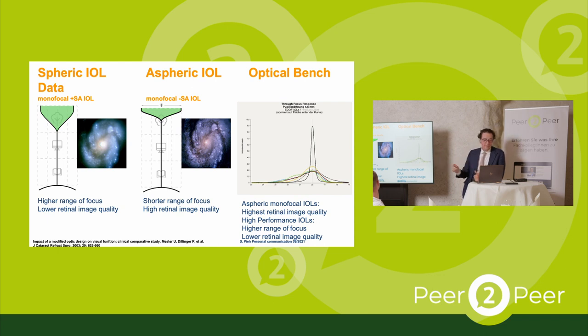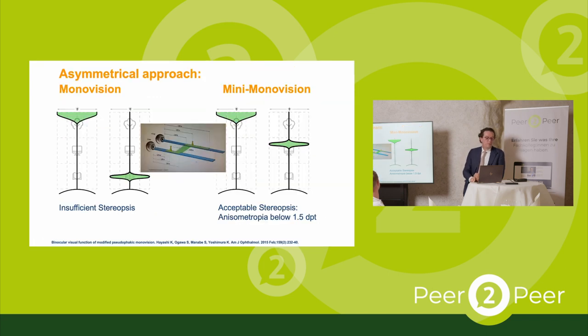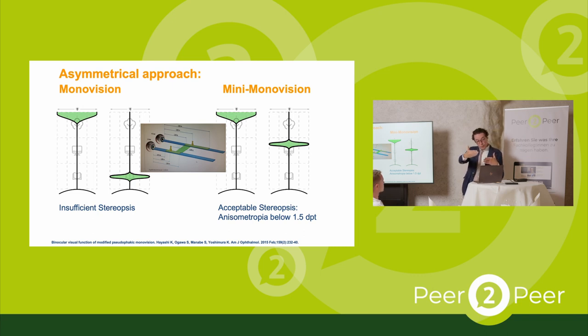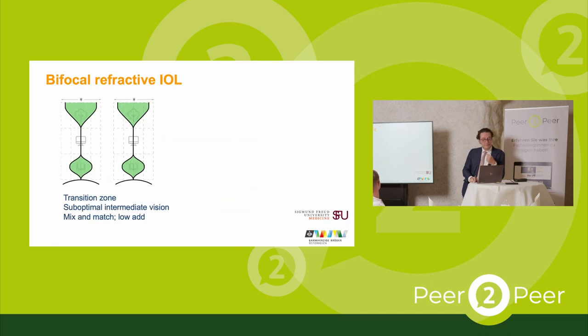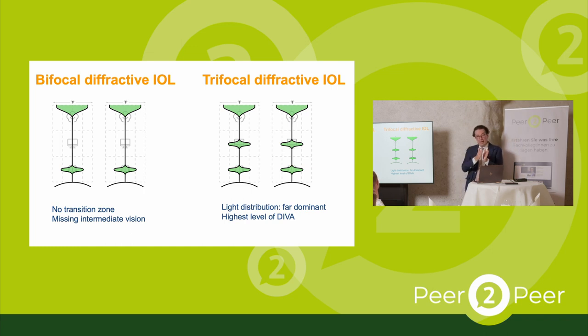On the optical bench, it's interesting: when doing EDOF testing, some of these lenses have more than one peak. If you have more than one peak, you definitely have a multifocal lens. We may also use asymmetrical monovision with EDOF lenses to extend visual ability to near. Bifocal refractive lenses have a wider near function area; diffractive lenses have a more precise, shorter focus line — bifocal or trifocal diffractive.